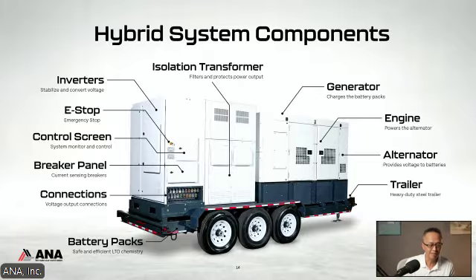Here, this product is mobile, so weight is a factor, but at the same time, because you have fuel on board, you don't need a massive battery, since 200 gallons of diesel gets you about 2.4 megawatt hours of energy. Power density is important here because if you could get away with less batteries, then you could cycle it more.